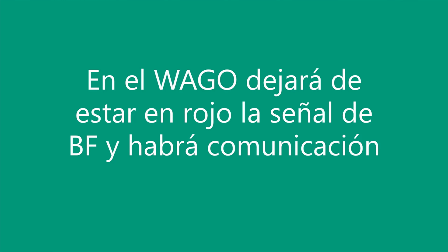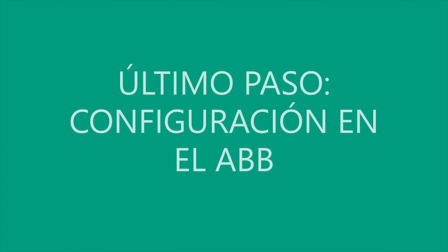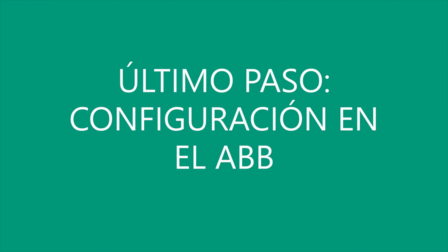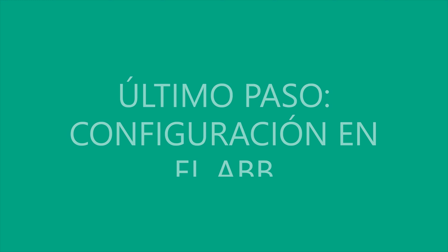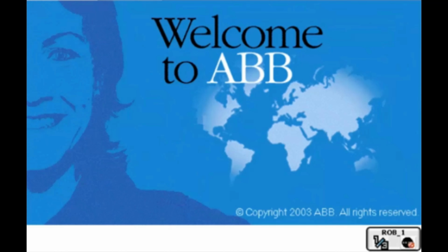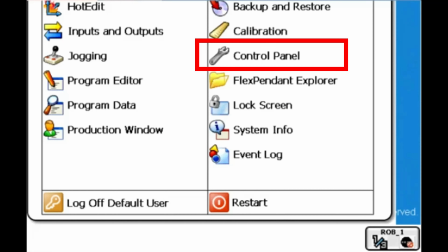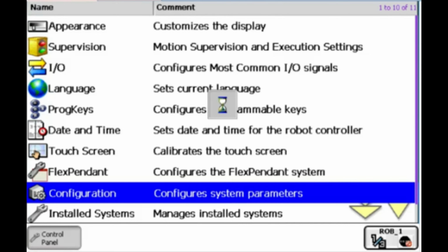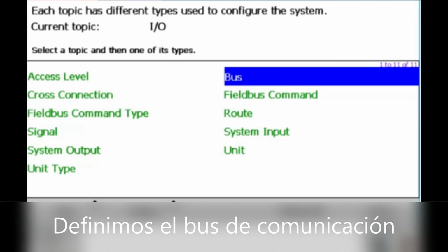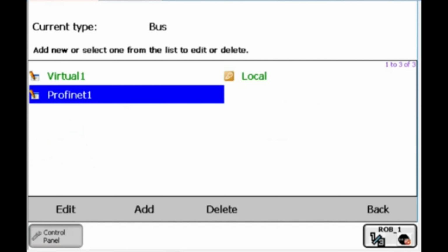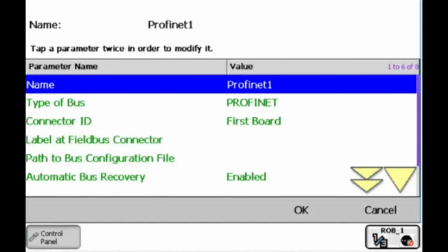Last part is to map all the inputs and outputs we assigned in the TIA Portal, which are 8 inputs and 8 outputs. So these are the last steps on the ABB. The first thing to do is go into Control Panel, and inside Control Panel, you go to Configuration. In Configuration, you need to create a bus. That's the PROFINET bus. Here you can see PROFINET 1. The connector ID has to be first board, remember that.